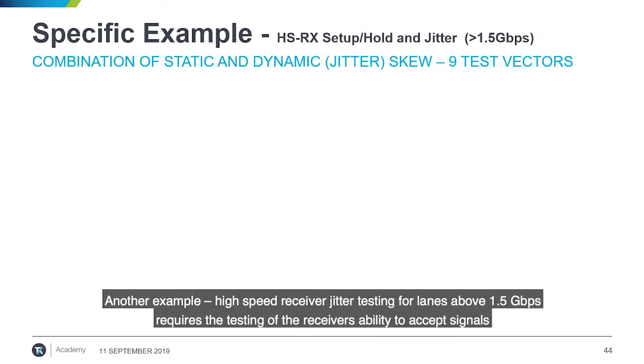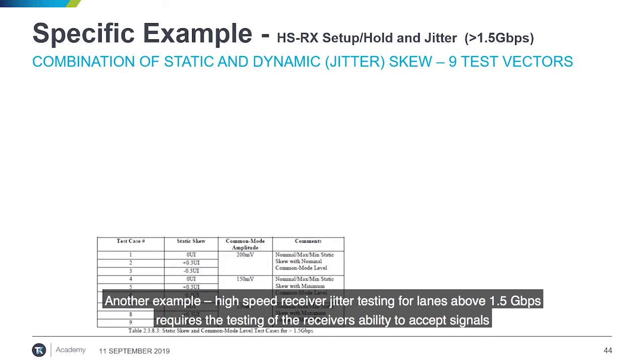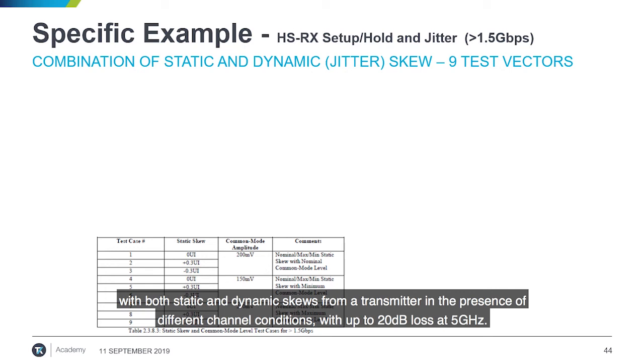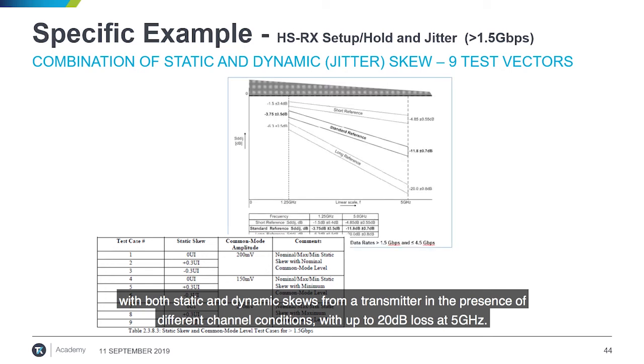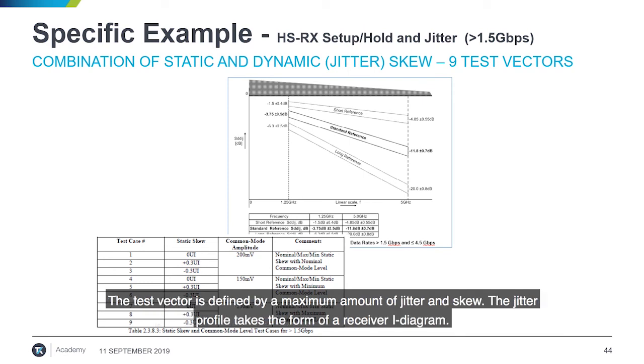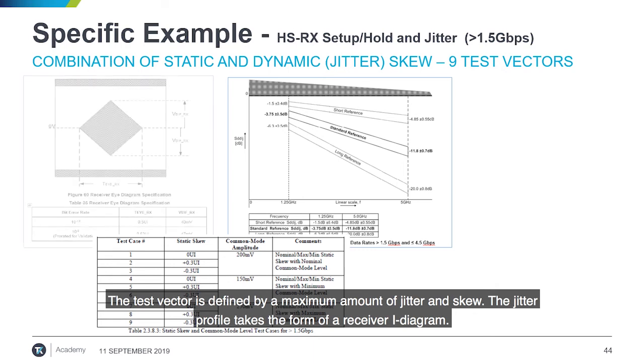Another example, high-speed receiver jitter testing for lanes above 1.5 gigabit per second, requires the testing of the receiver's ability to accept signals with both static and dynamic skew from a transmitter in the presence of different channel conditions, with up to 20 dB loss at 5 GHz. The test vector is defined by a maximum amount of jitter and skew. The jitter profile takes the form of a receiver eye diagram.